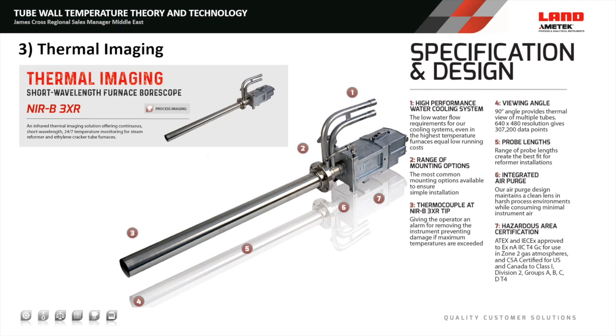The third method is thermal imaging technology. This is an example of our shortwave boroscope, the NIR-B3XR. With cooling water and purge air installed, it can be permanently installed in a reformer. The purge air ensures no hot gases are in permanent contact with the lens, and cooling water keeps all electronics below 45 to 50 degrees C. With a 90-degree viewing angle, placing the lens at the edge of the refractory allows you to see many tubes in a single aisle. Installing multiple cameras can give up to 90 to 95 percent coverage of all tubes in a reformer.